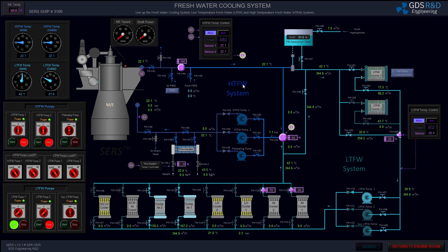In this video I will line up the high temperature fresh water system. As you can see, the main engine temperature is about 22 degrees. I will perform a preheating operation with steam and heat the main engine up to 60–65 degrees.